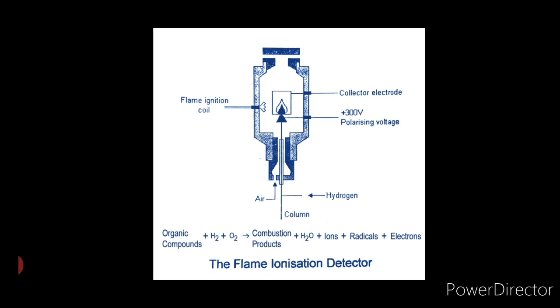A flame supported by hydrogen gas and air is used to burn organic vapors as they leave the column. Electrons and ionic fragments are produced upon combustion of the organics. This is the reaction that takes place: organic compounds plus H2 plus O2 gives us combustion products plus H2O plus ions plus radicals plus electrons.